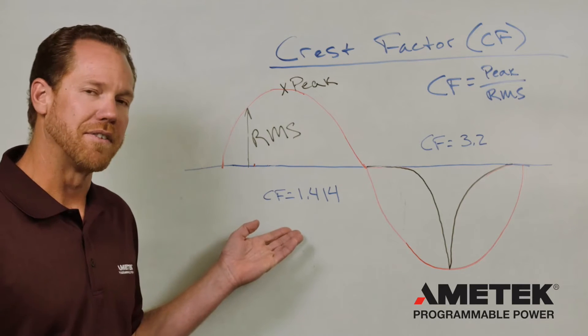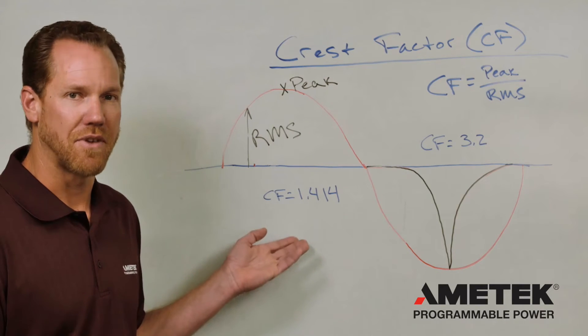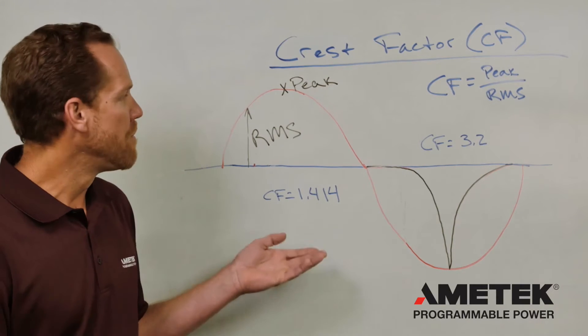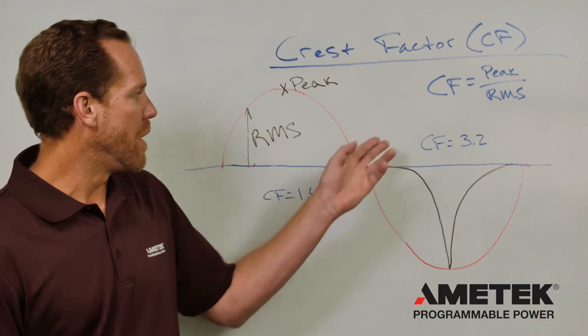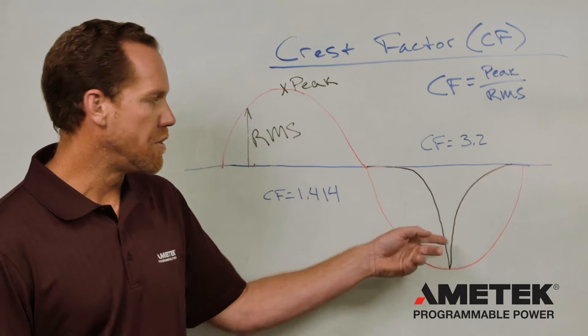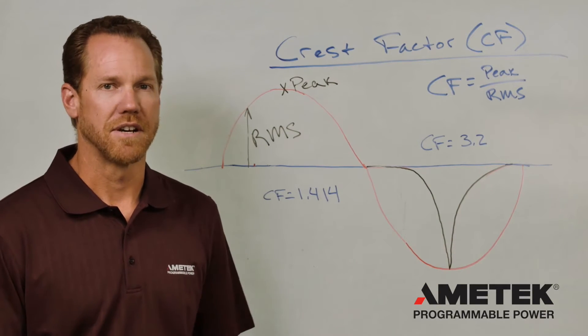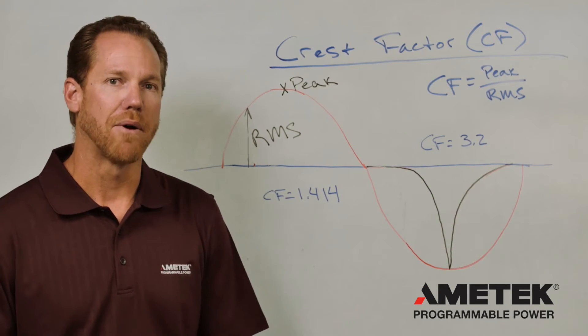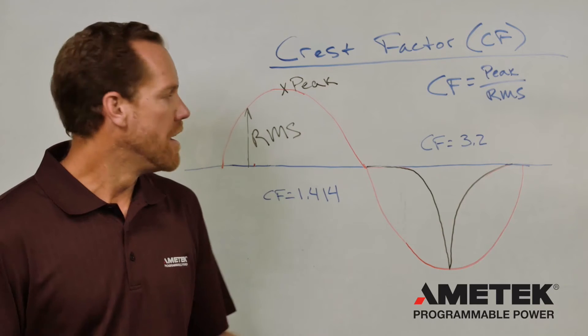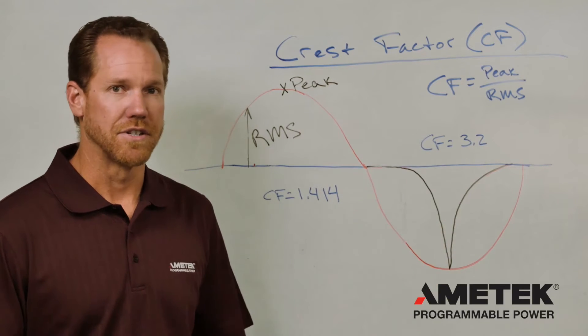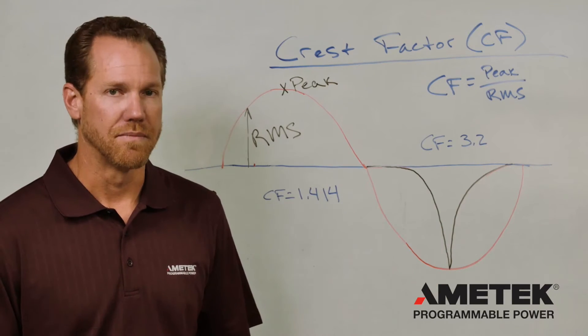A perfect sine wave has a crest factor of 1.414. A waveform like this, where you might have a peakier waveform — such as a rectified power supply — you get a higher crest factor, such as 3.2.